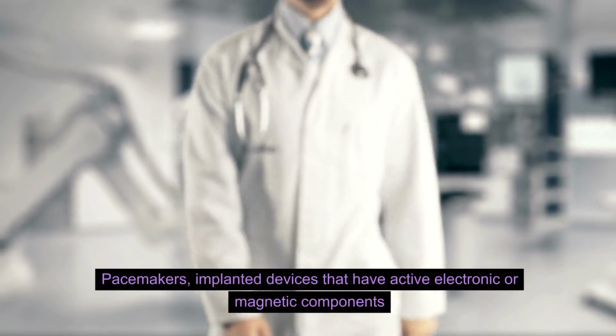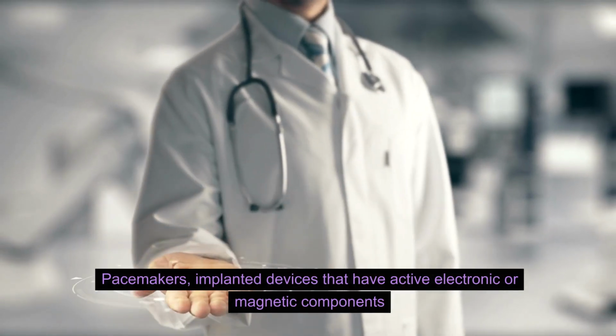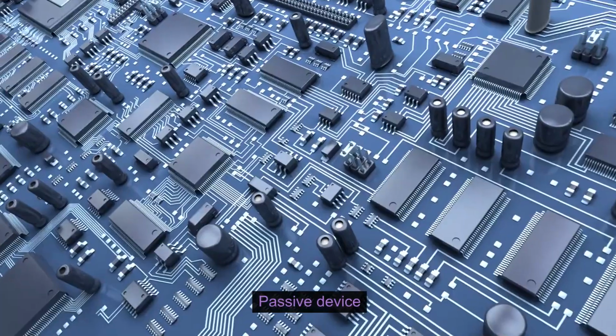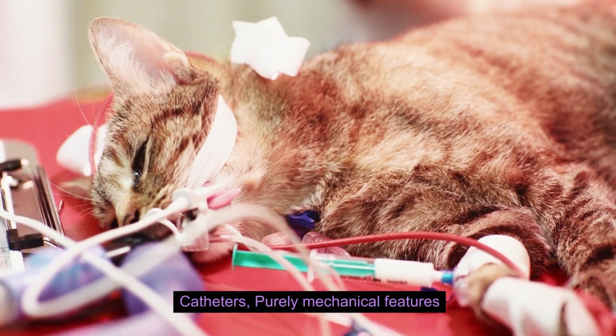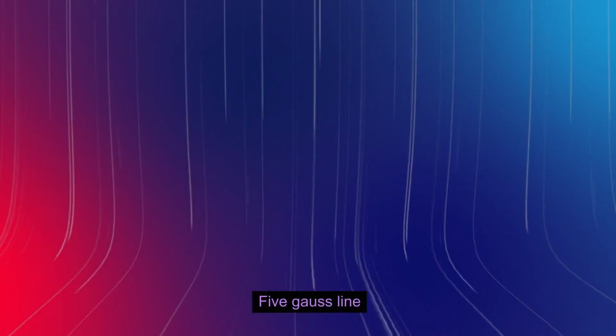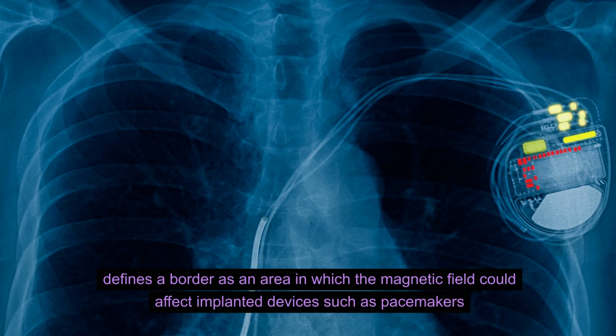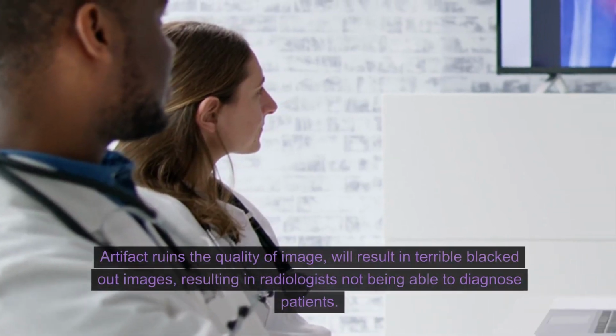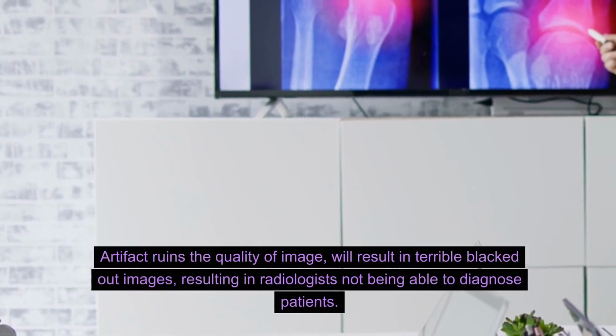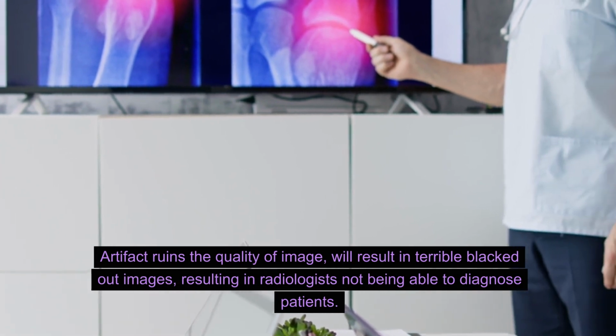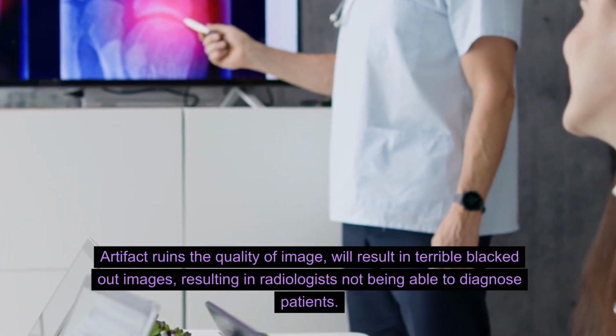Terms: active device, pacemakers, implanted devices that have active electronic or magnetic components; passive device, catheters, purely mechanical features. 5 Gauss line. Defines a border as an area in which the magnetic field could affect implanted devices, such as pacemakers. Image artifact. Artifact ruins the quality of the image, will result in terrible blacked out images, resulting in radiologists not being able to diagnose patients.